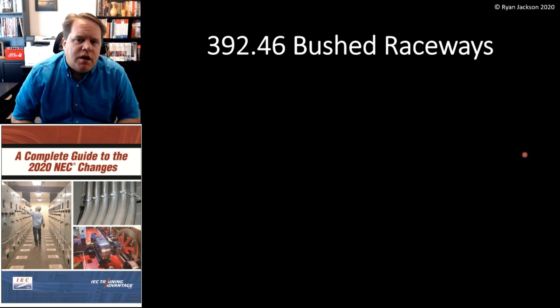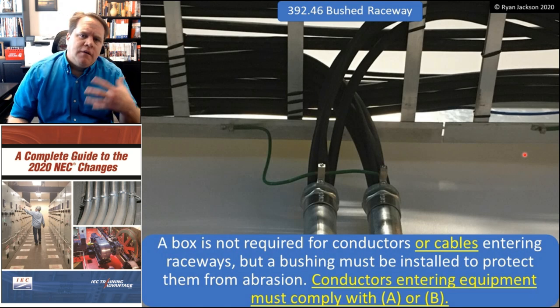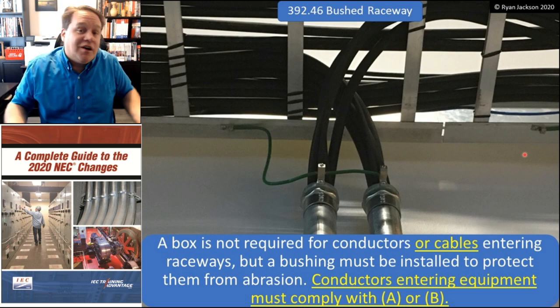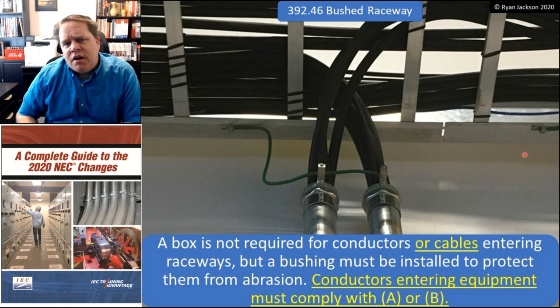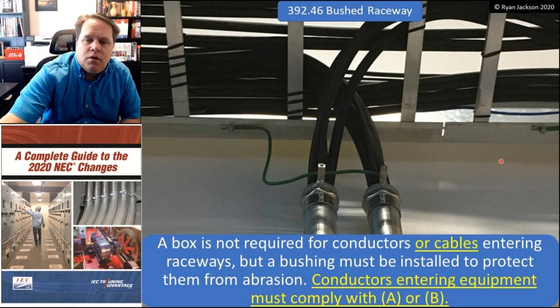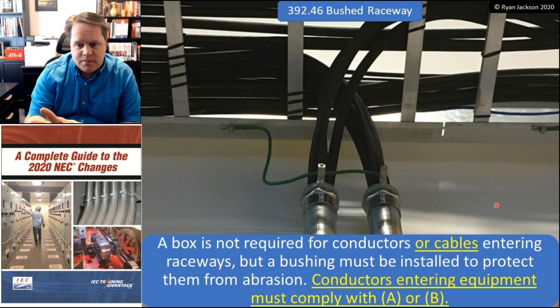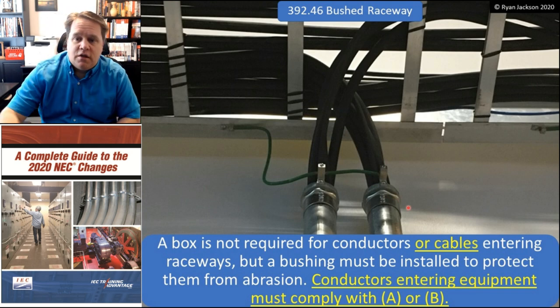The last change in the 2020 NEC for cable trays is 392.46 — new requirements for a common practice were added. It's funny how we'll do something for a hundred years and the code doesn't actually talk about it. So 392.46 Bushed Raceways: a box is not required for conductors or cables entering raceways from a cable tray, but a bushing has to be installed to protect them from abrasion. Conductors entering equipment must comply with A or B.